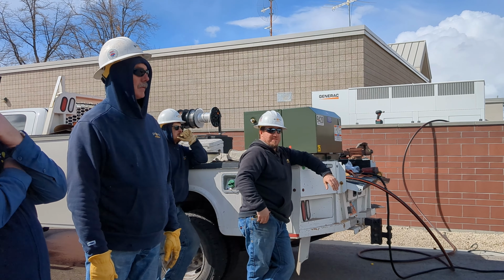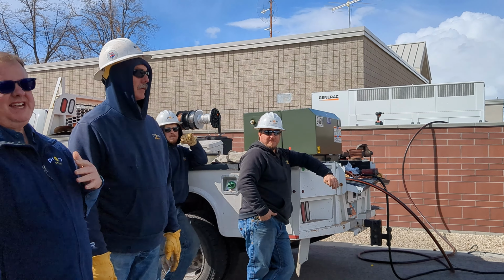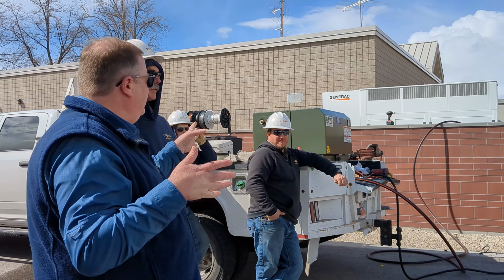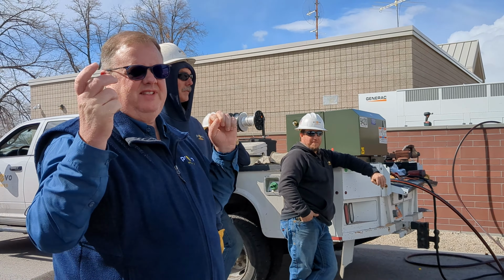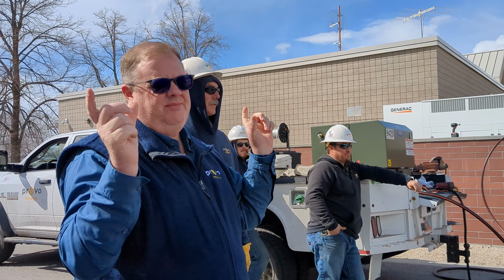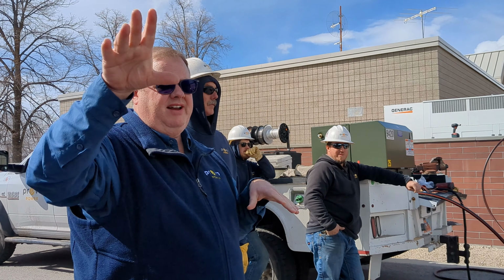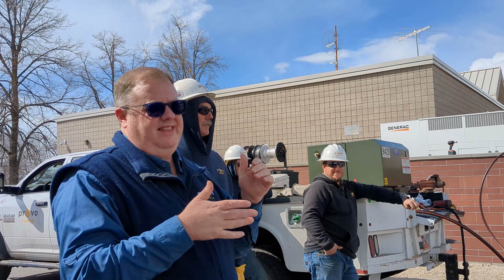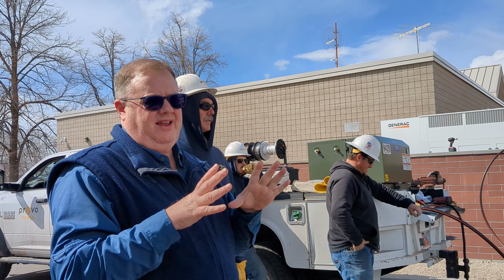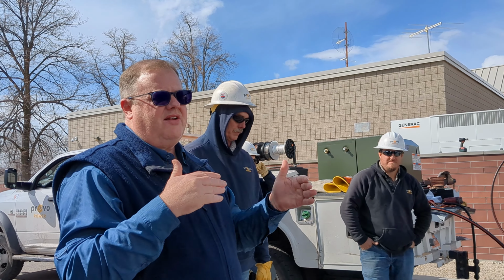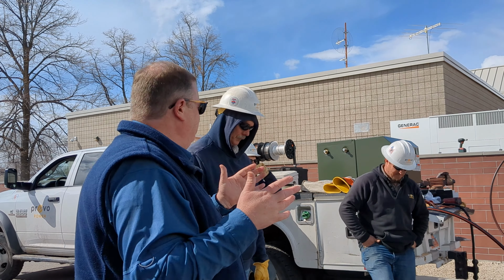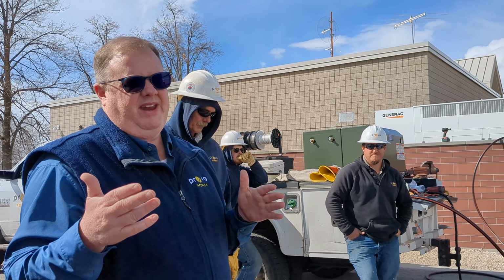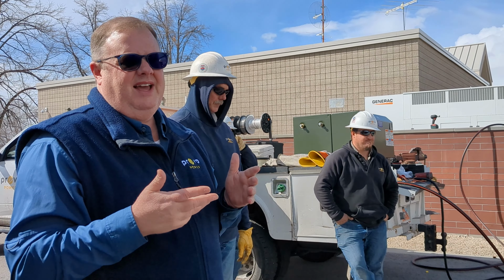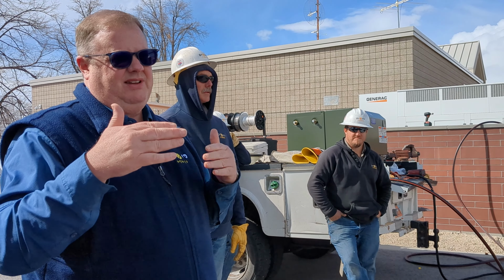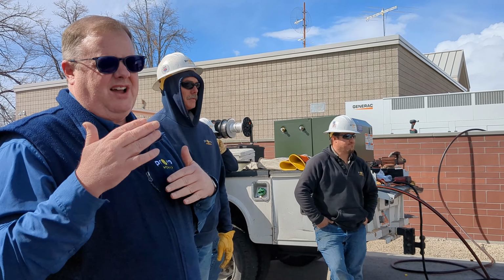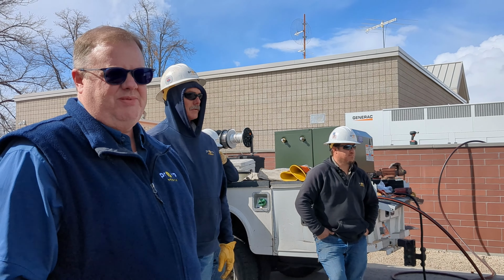fault on this fuse. We have sectionalizers. You have smart sectionalizers. They're putting up switches now that have CTs and PTs on them. So in the downtown area, if there's a fault in an area, it'll reroute the power without any lineman being there. So there are things to do that. What happens is, is it worth the money, right? Do you put all that money in, and what is the incremental change on reliability? So you kind of have to weigh the cost benefit of those type of things.